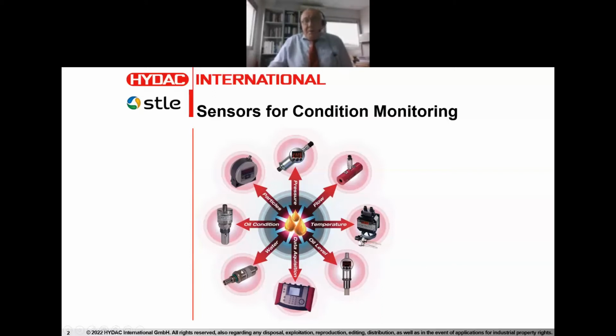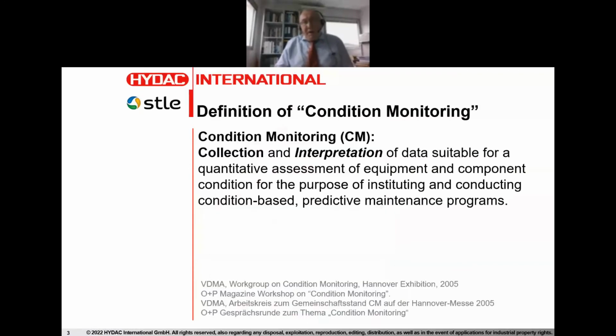And these include things like water relative humidity determination in oils, oil condition that includes also dielectric constant, conductivity. At the beginning, we also had viscosity sensor head in it. Unfortunately, that didn't necessarily pan out. Particle counters, pressure sensors, flow sensors, temperature sensors, oil level sensors, and so on. And once we provide this distributed sensor array and install it all over all the operating equipment in a particular plant, then we can collect a signal on a single analyzer and examine it at a later, more convenient time, or we can monitor it live.